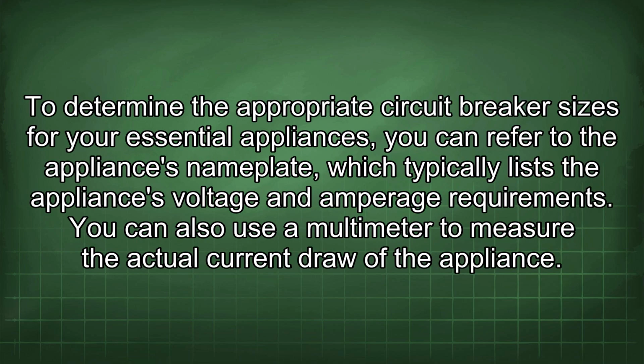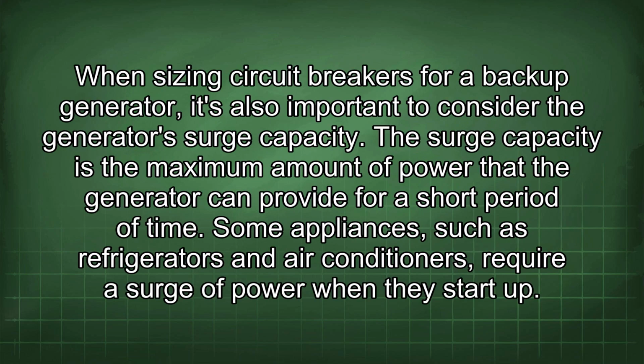To determine the appropriate circuit breaker sizes for your essential appliances, you can refer to the appliance's nameplate, which typically lists the appliance's voltage and amperage requirements. You can also use a multimeter to measure the actual current draw of the appliance. When sizing circuit breakers for a backup generator, it's also important to consider the generator's surge capacity. The surge capacity is the maximum amount of power that the generator can provide for a short period of time.